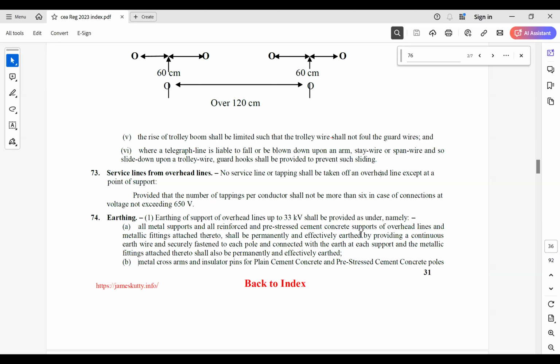So there should not be any such controversy that when the distance increases, the protection has to be reduced. The breaker cost is hardly maybe 50,000, 60,000 or below a lakh for the 500 kVA and 630 kVA transformer. Below this rating capacity, whether it is 100 kVA or 1000 kVA, from the electrical system point of view, we have to have a complete protection system on all the aspects. That is one.